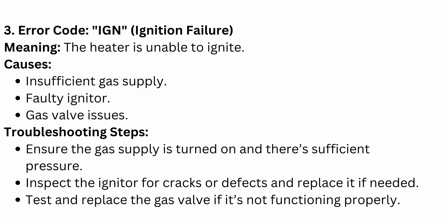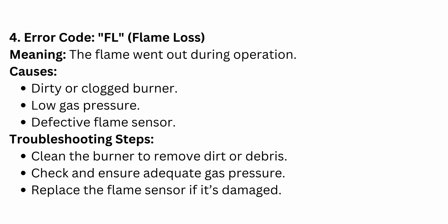Another code is IG, which stands for Ignition Failure — the heater is unable to ignite. Causes can be insufficient gas supply, a faulty igniter, or gas valve issues. To troubleshoot: ensure the gas supply is turned on with sufficient pressure, inspect the igniter for cracks or defects and replace if needed, and test and replace the gas valve if it is not functioning properly.